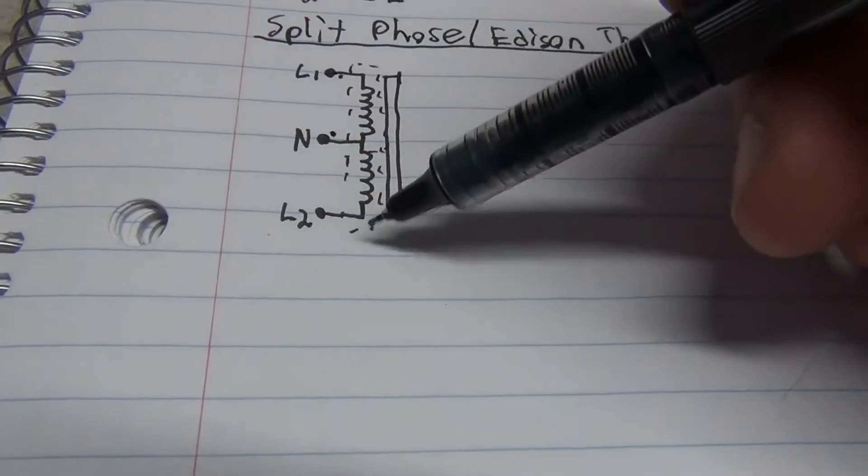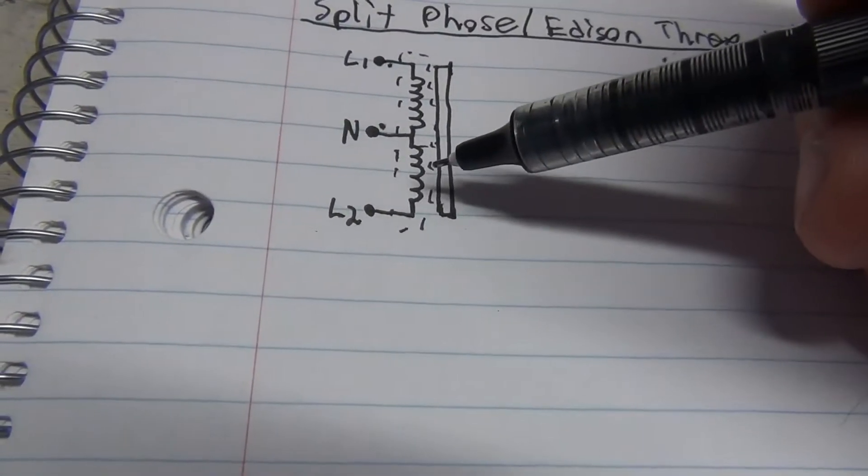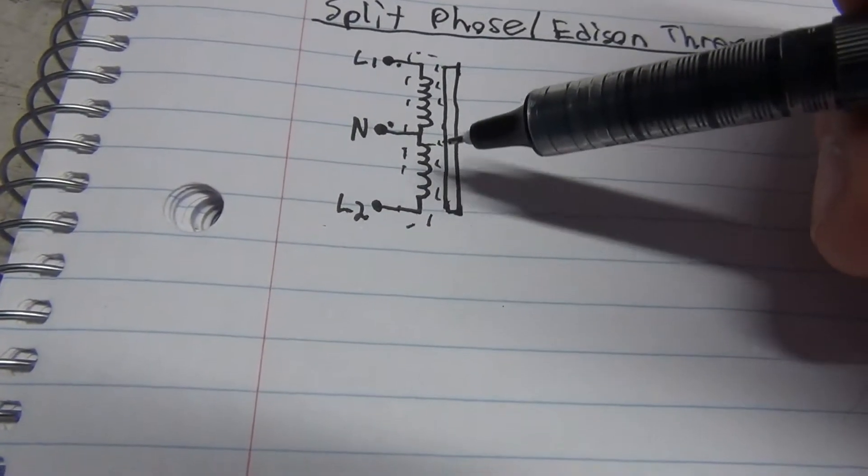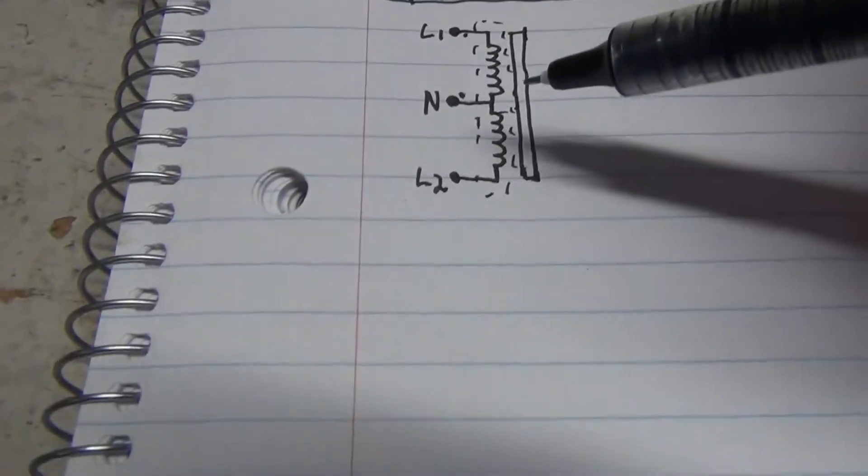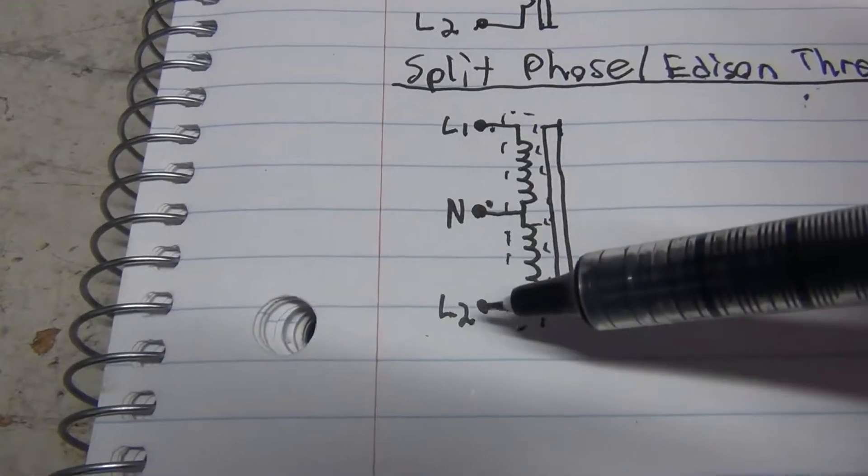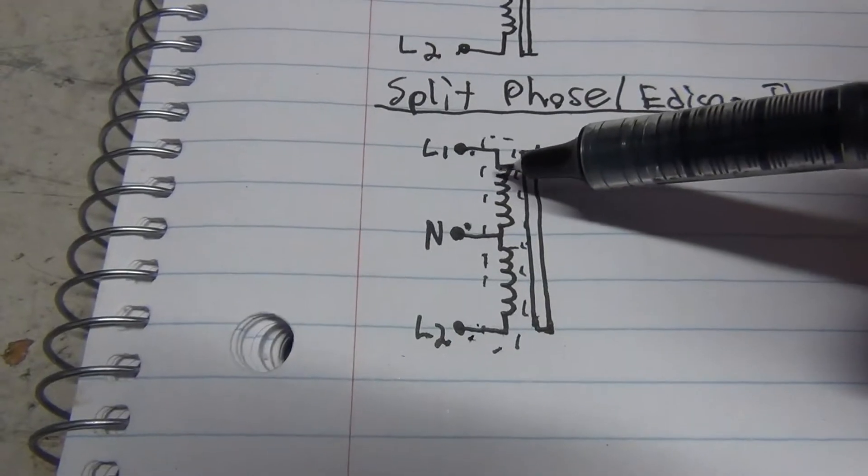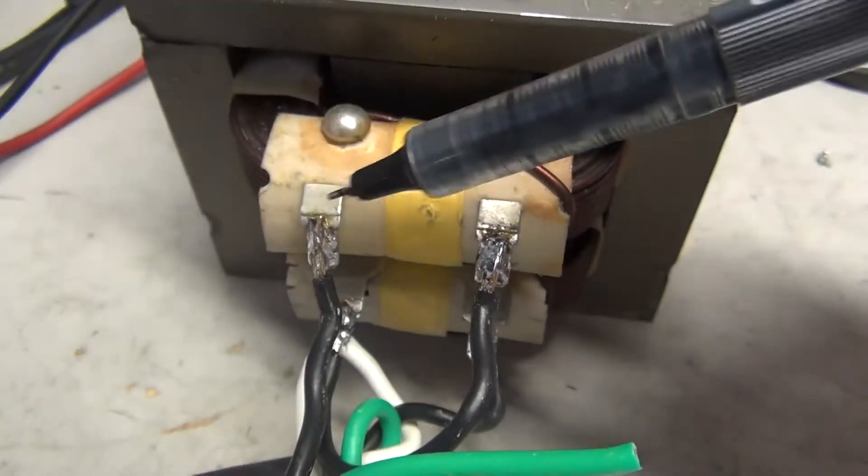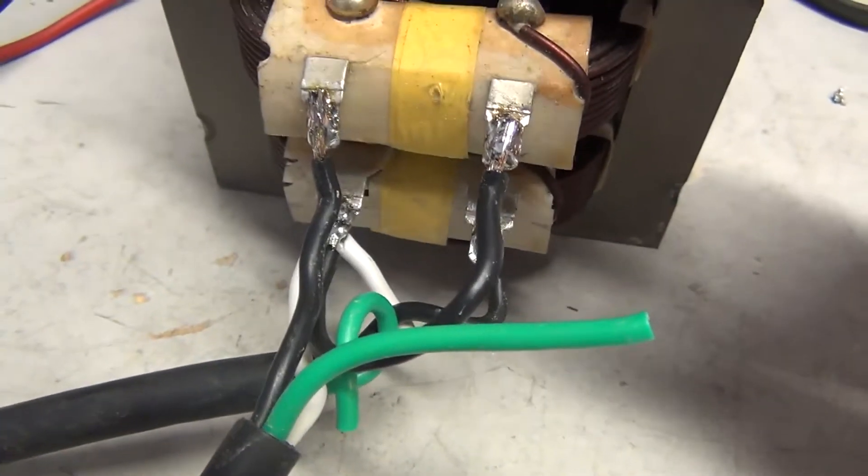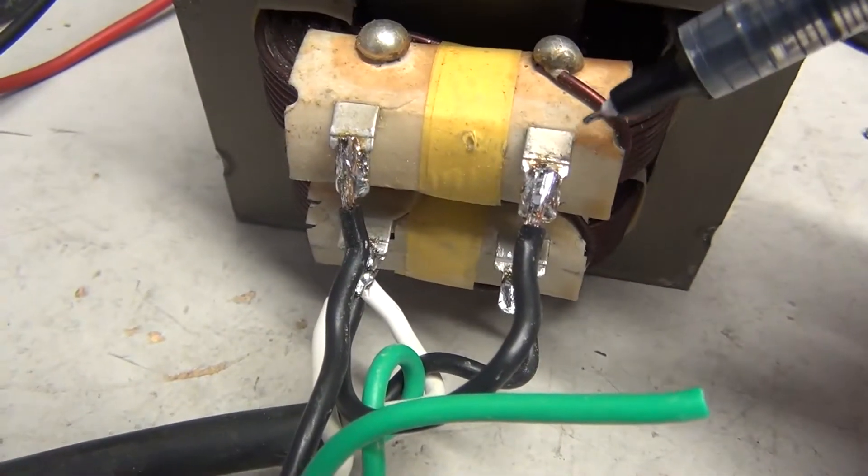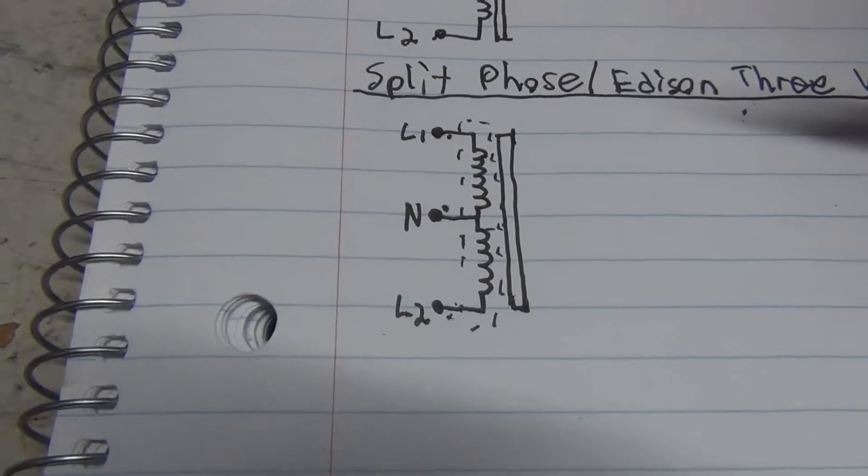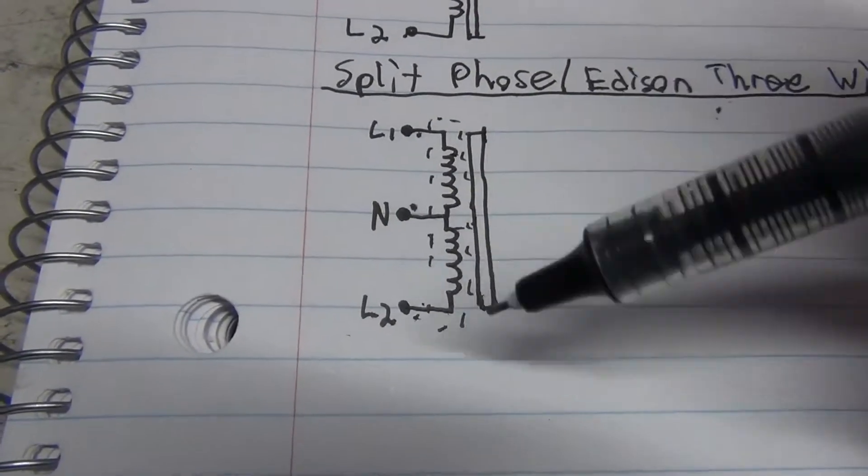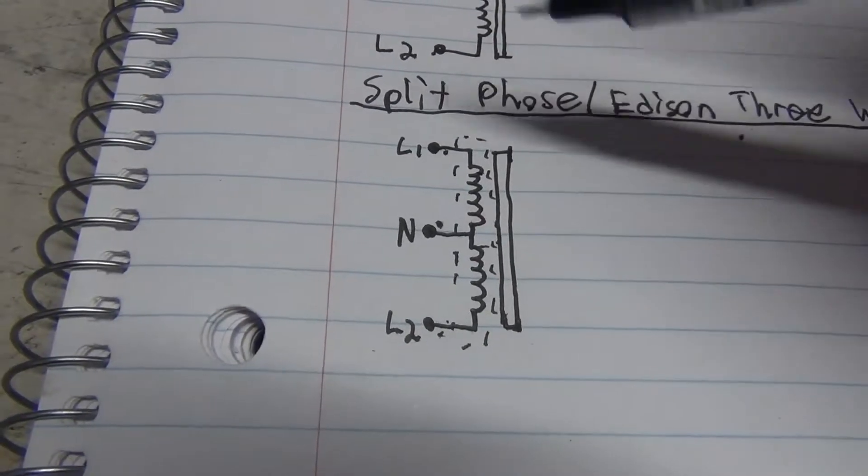And then on this side rather than going in series like the first configuration, you have to phase your winding. You want the voltage from here to be 180 degrees out of phase from here. So you just have to switch these two leads until on your multimeter you'll get 240 volts from line 2 to line 1. That's essentially a center-tapped auto transformer.